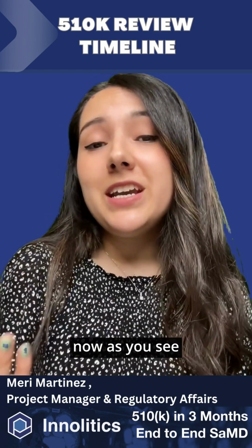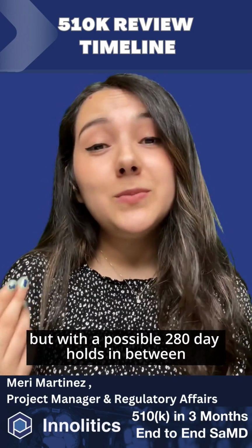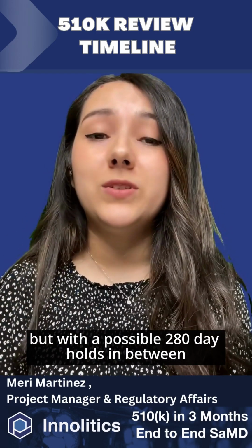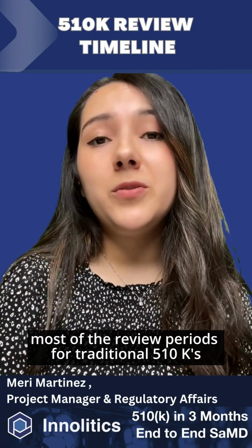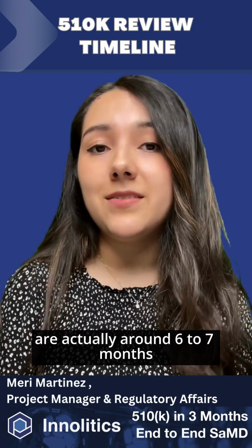Now, as you see, FDA's review clock is around 90 days, but with a possible 180-day holds in between, most of the review periods for traditional 510(k)s are actually around 6 to 7 months.